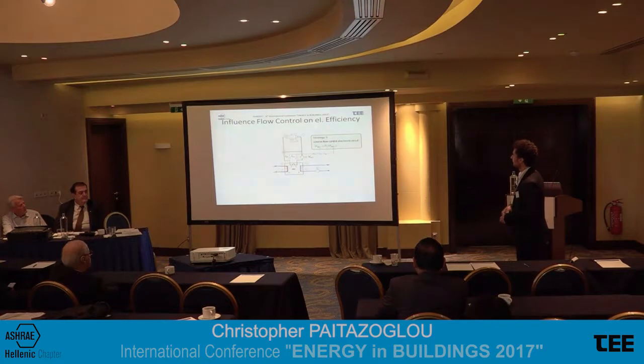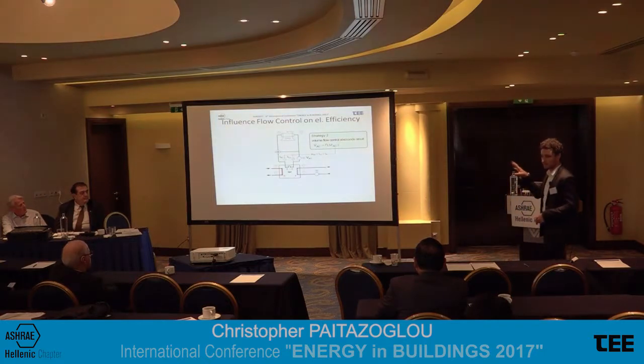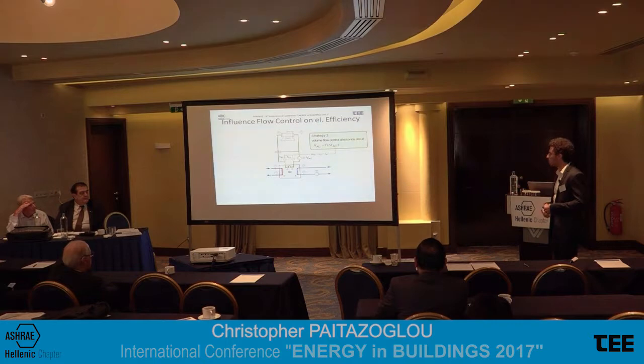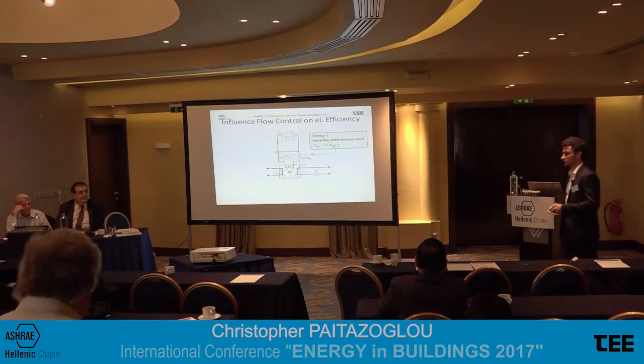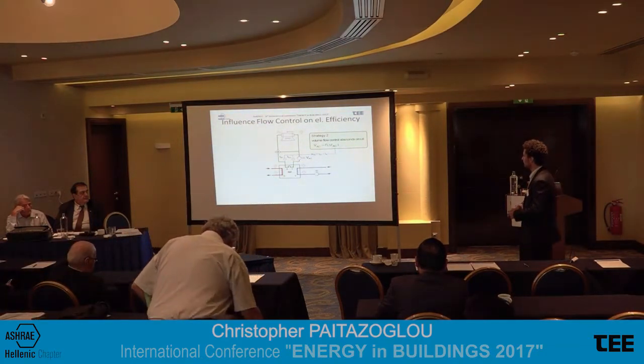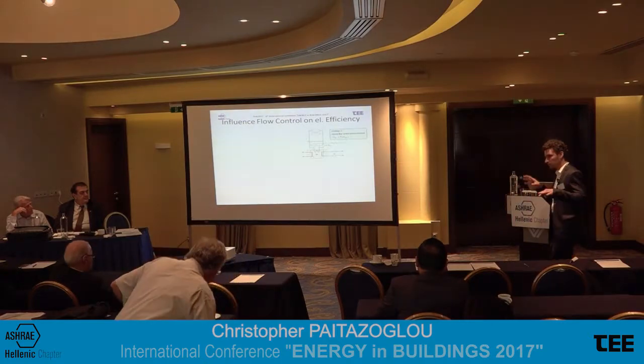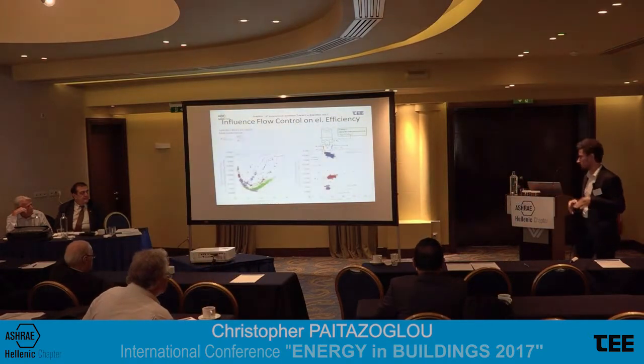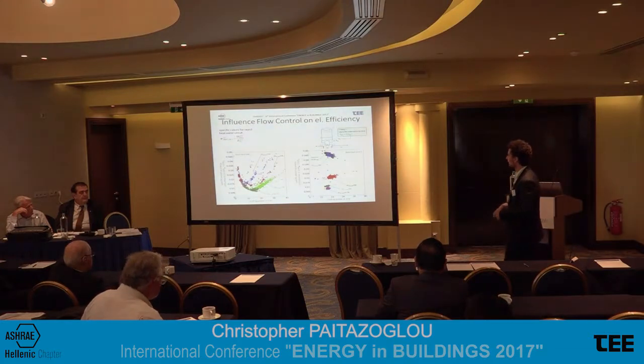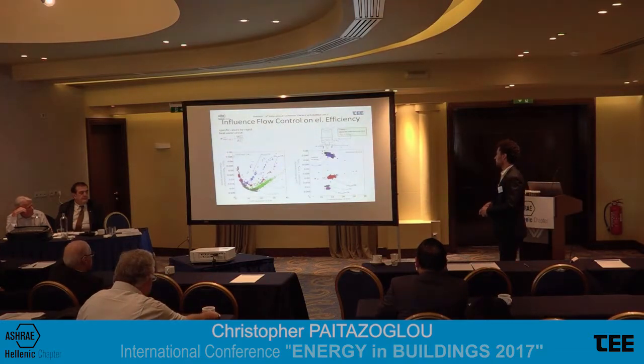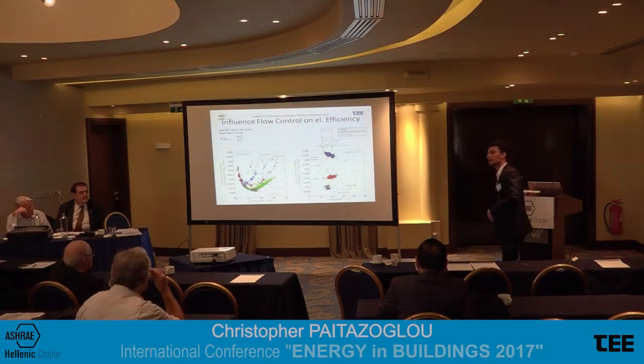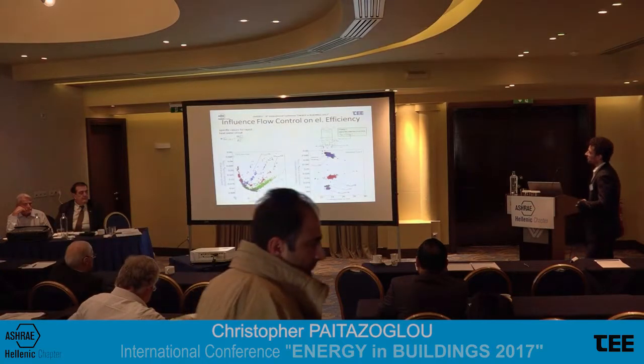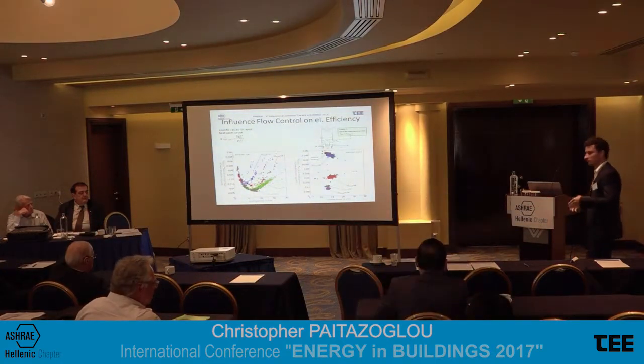Okay. So maybe you remember the second strategy, which was volume flow control of this pump here. What is the outcome if we operate that with different set points? Set points meaning this temperature difference here. I selected 2 sites where we implemented those control strategies in the last months. On the left side, a field test with a very volatile cooling capacity, and on the right side, a field test with a very constant cooling load, as it was in an IT center.